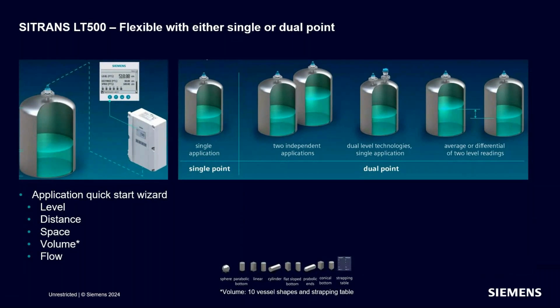However, using a dual channel unit, you can do independent applications, 2 different vessels through 1 controller. You can do dual level with redundant or different technologies, meaning you could have an ultrasonic on one and a radar on the other, so that if one technology would for some reason fail, the other one would not.